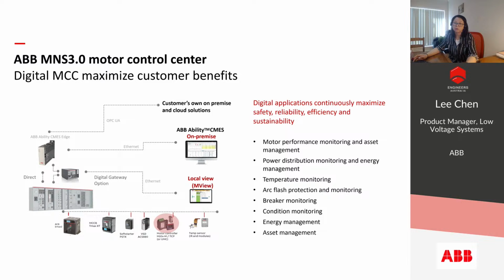The extensive amount of information collected by the smart devices and sensors is then reported to a data concentrator through an Ethernet-based digital network, where correlated data are compared, studied, and analyzed. In MNS3, the data concentrator can be an ABB switchgear gateway device installed on a switchboard to provide centralized parameterization, automation, and control. The data concentrator can also be a CMES hub to collect multiple switchgear information and provide applications such as 24/7 online condition monitoring for analysis and solution suggestions, energy consumption analysis and reports, etc.